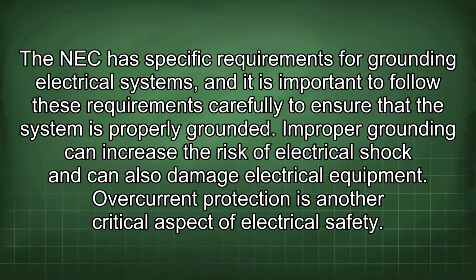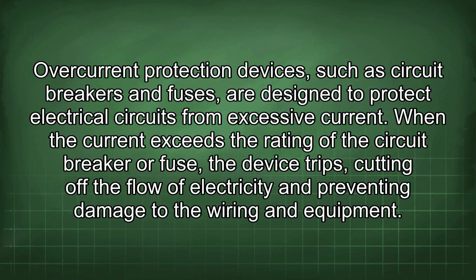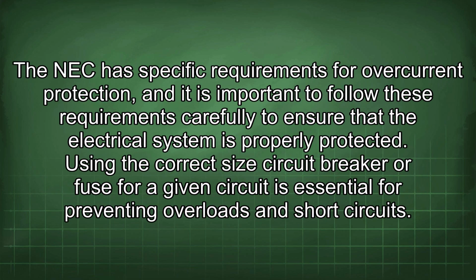Overcurrent protection is another critical aspect of electrical safety. Overcurrent protection devices such as circuit breakers and fuses are designed to protect electrical circuits from excessive current. When the current exceeds the rating of the circuit breaker or fuse, the device trips, cutting off the flow of electricity and preventing damage to the wiring and equipment. The NEC has specific requirements for overcurrent protection, and it is important to follow these requirements carefully to ensure that the electrical system is properly protected. Using the correct size circuit breaker or fuse for a given circuit is essential for preventing overloads and short circuits.